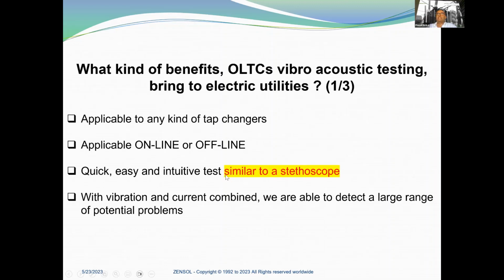We have an advertising image, a picture where you see a high voltage transformer coming in to a vibro therapy room, and with a stethoscope the doctor is able to listen to the high voltage transformer speaking, or in fact vibrating. So with vibration and current combined, we're able to detect a large range of potential problems.